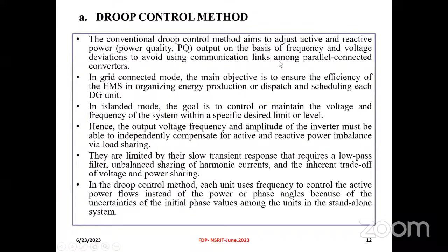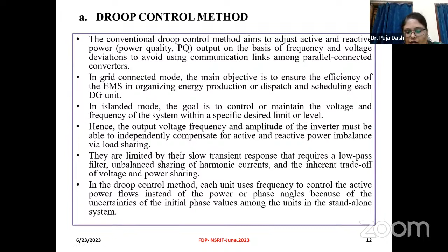In droop control, each unit uses frequency to control the real power flow instead of power and phase angles, because of uncertainties in the initial phase mechanism of the unit in a standalone system. There is a defined change in frequency to regulate voltage. Frequency governs real power flow, and voltage governs reactive power flow; this forms the droop control strategy.